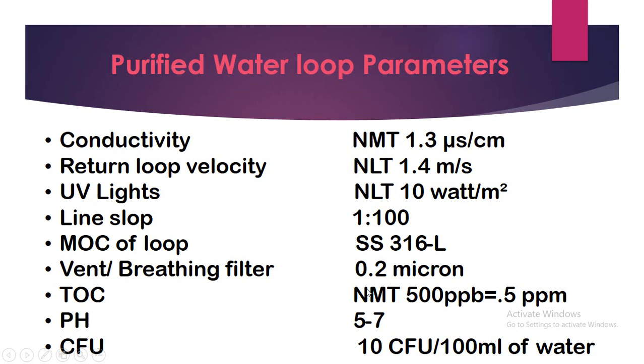TOC should be not more than 500 ppb, which is equal to 0.5 ppm. pH should be 5 to 7, and CFU should be less than 10 CFU per 100 ml of water. These are the maximum acceptable ranges.